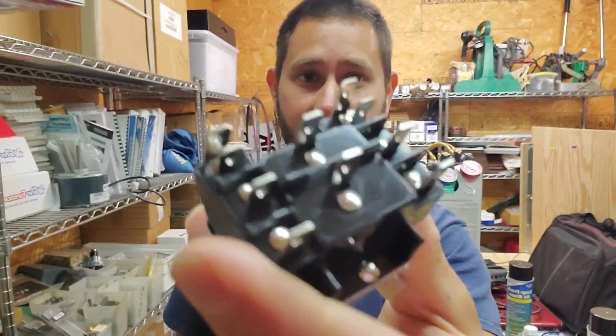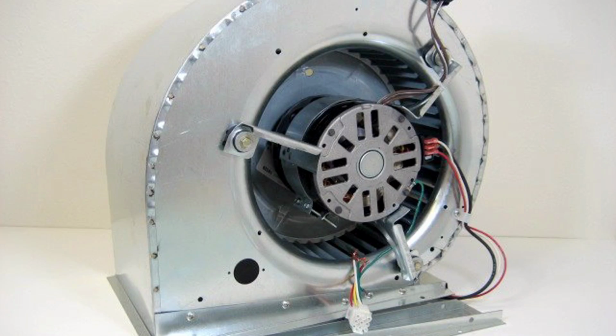I've had units that are intermittently shutting on and off and on and off because they had a bad relay, and that was causing the unit to intermittently freeze. If your evaporator fan is not pushing the proper amount of airflow through that coil, then it's going to cause a lower pressure and it's going to cause it to freeze.